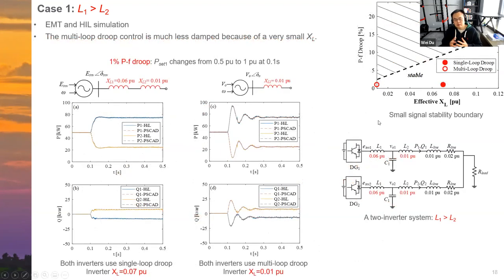And then here, let's do some time domain EMT simulations and also hardware in loop simulation. You can see that for case one, L1 larger than L2, if we use 1% droop gain and change the set point of one inverter, for the left side, the single loop droop control, the system is pretty damped. This is because they have larger coupling reactance. And for the right side, with the same disturbance, if both inverters use the multi-loop droop control, we can see some oscillations between the two inverters because of the much smaller coupling reactance.